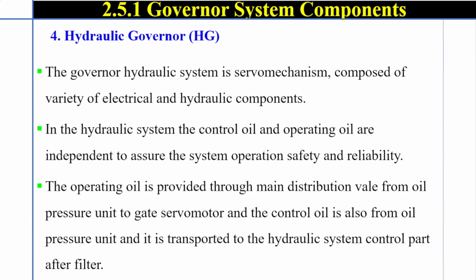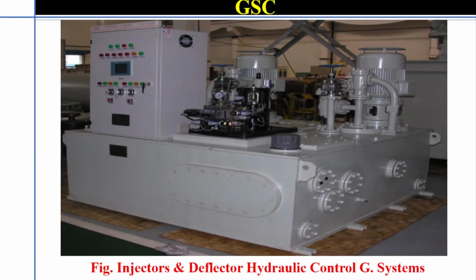The fourth type of governor system component is the hydraulic governor. The governor hydraulic system is a servo mechanism composed of a variety of electrical and hydraulic components. In the hydraulic system, the control oil and operating oil are independent to assure the system's operational safety and reliability. The operating oil is provided through the main distribution valve from the oil pressure unit to the gate servo motor, and the control oil is also from the oil pressure unit, and it is transported to the hydraulic system control part after filter. This picture indicates the injector and deflector hydraulic control governor systems.